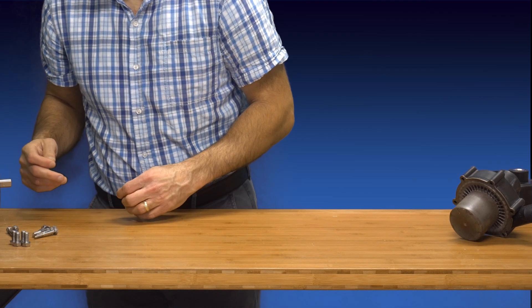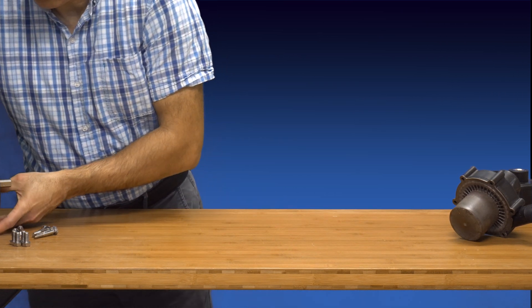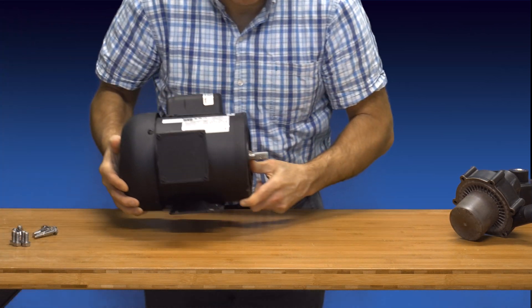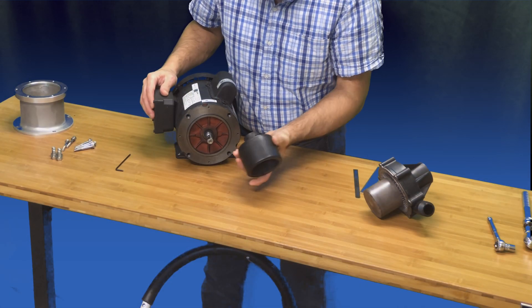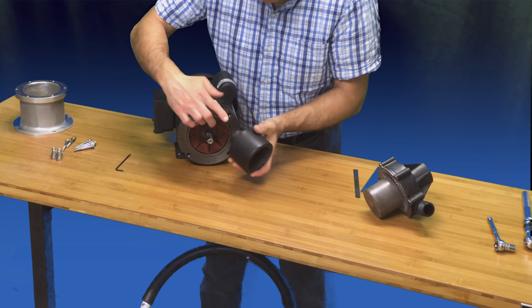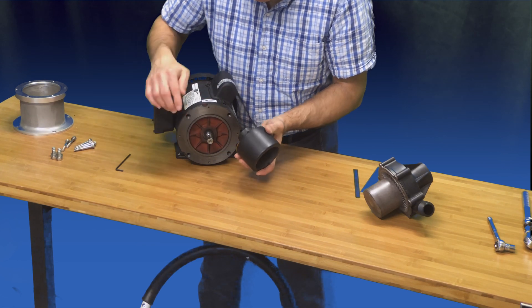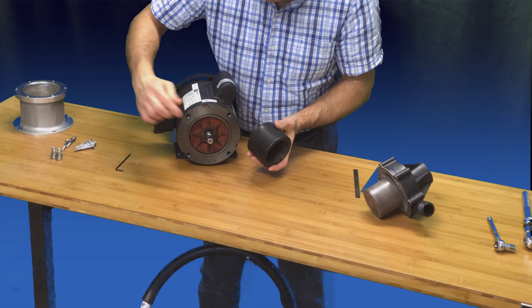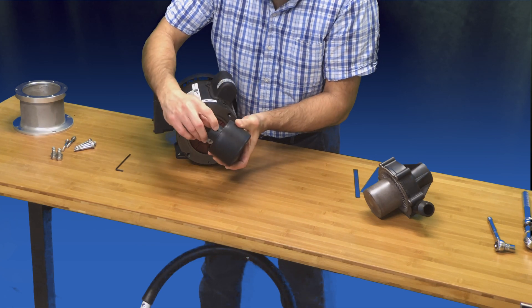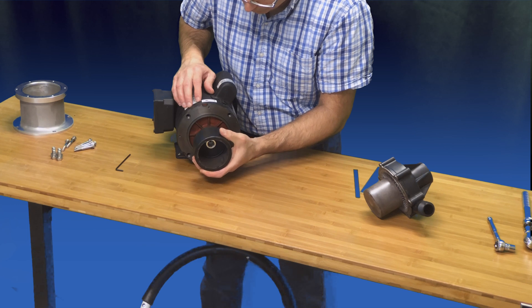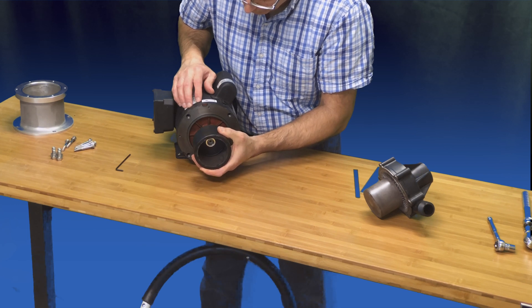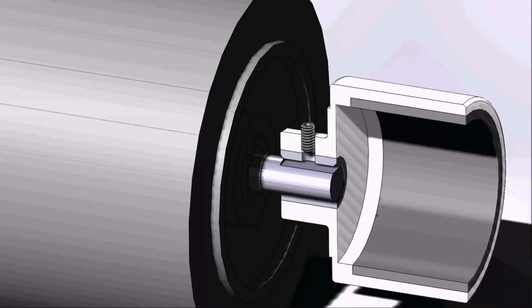Next, prepare to install the drive magnet assembly. Position the motor in front of you. Be sure that the power has been disconnected from the motor when working on it. Rotate the motor shaft so that the flat on the shaft is facing up and hold the drive magnet assembly so that one of its set screws is also facing up. Slide the drive magnet assembly onto the motor shaft and screw the set screw facing up slightly in, just enough to prevent the drive magnet assembly from rotating.